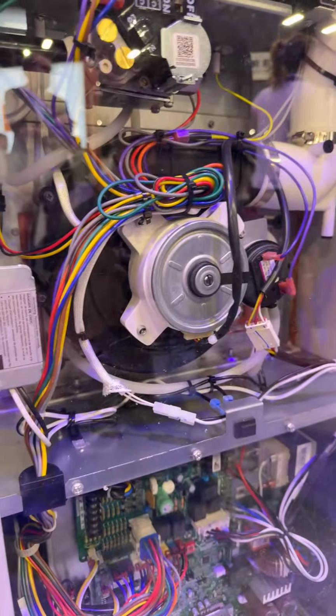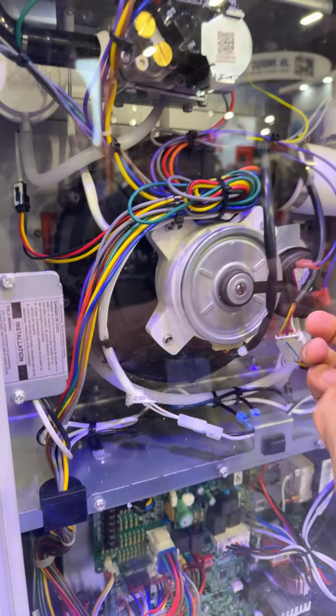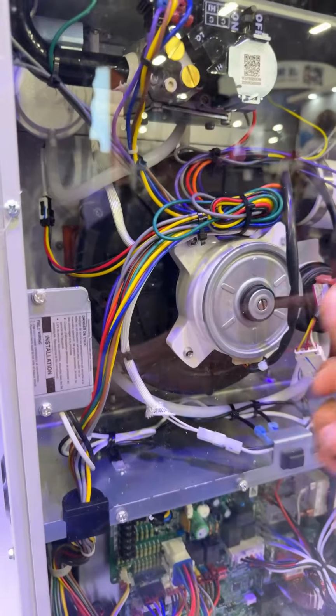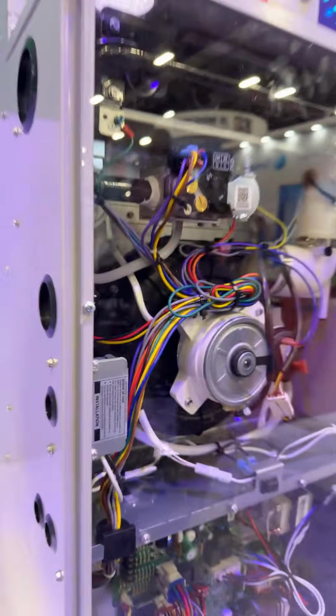If it measures a pressure difference greater than 0.25 inches of water column, this is normally closed. It opens up and it stops the command from going to your gas valve.